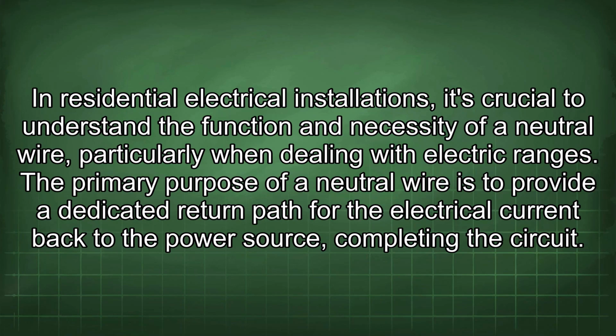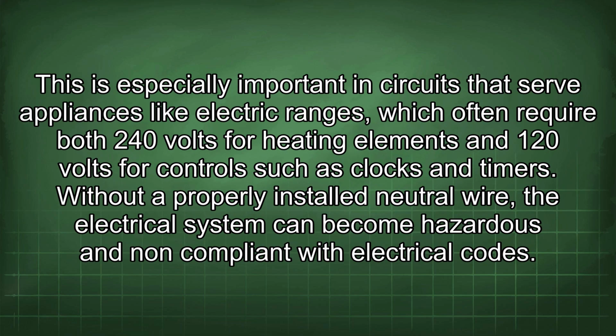In residential electrical installations, it's crucial to understand the function and necessity of a neutral wire, particularly when dealing with electric ranges. The primary purpose of a neutral wire is to provide a dedicated return path for the electrical current back to the power source, completing the circuit. This is especially important in circuits that serve appliances like electric ranges, which often require both 240 volts for heating elements and 120 volts for controls such as clocks and timers.